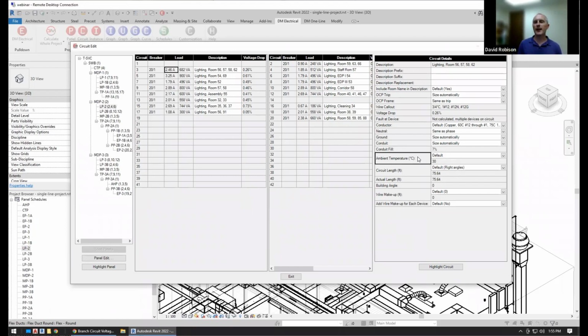After the conduit, we have the ambient temperature, and we use this to derate the wire if you set it something off the default. So if I go from 30 degrees to 45, it's going to have to upsize my wires to number 10 based upon that ambient temperature. Then we have the circuit length calculation. And there is actually a lot going on here as well. So we'll take a moment and walk through all of our different options.